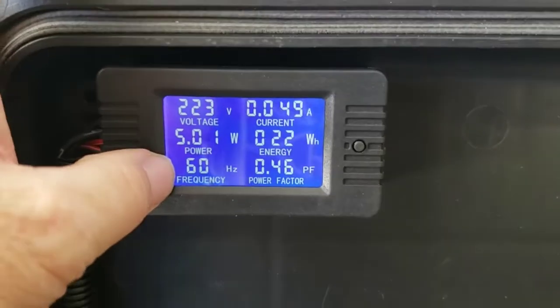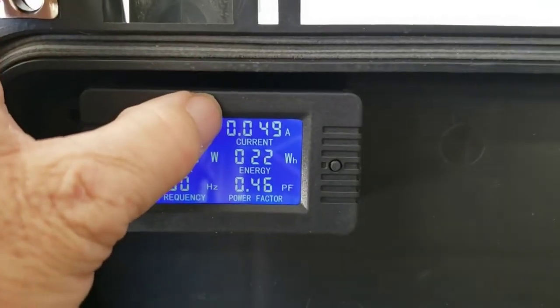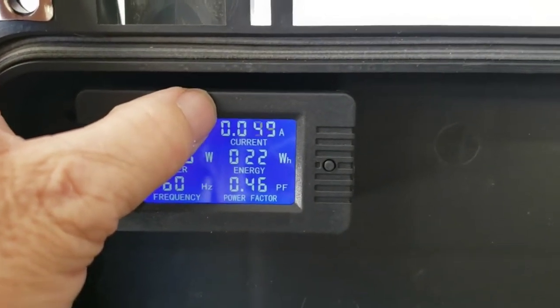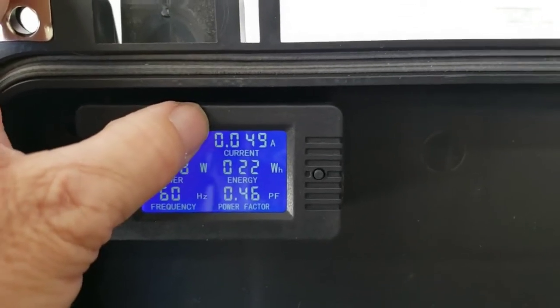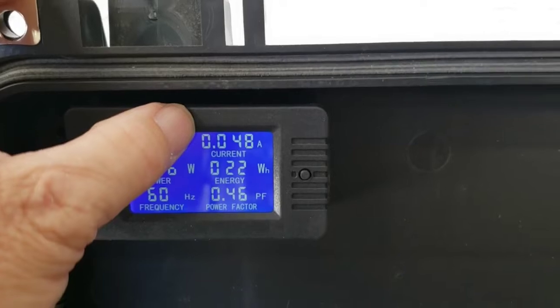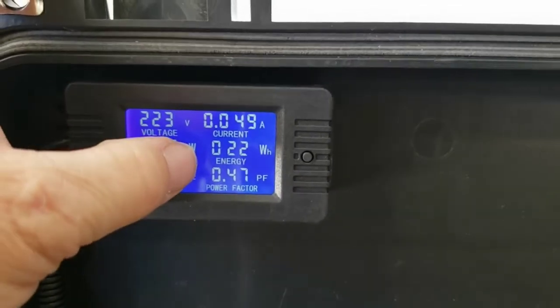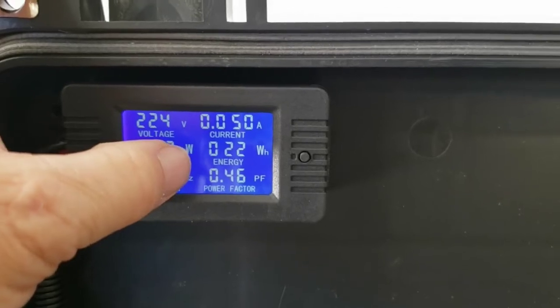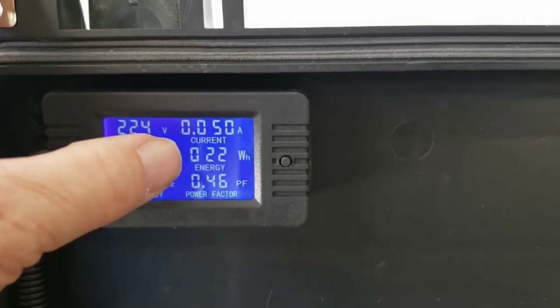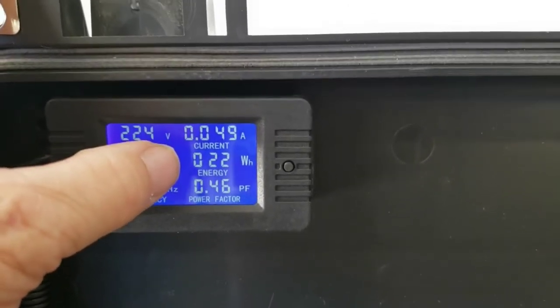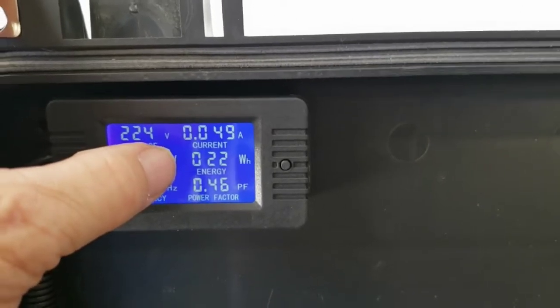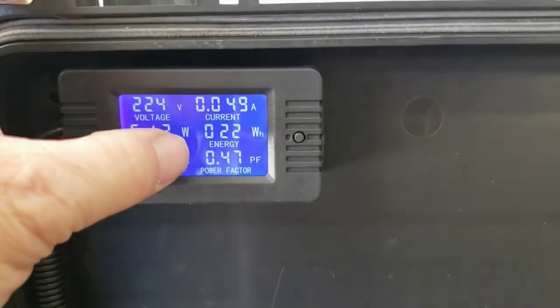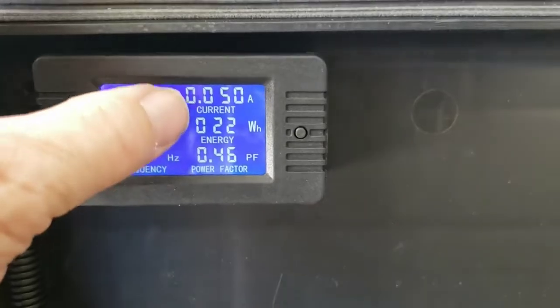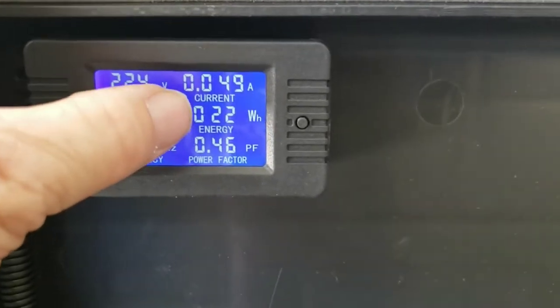Line frequency, 60 hertz of course. That'll display the amps that you're currently drawing at the 240 volt range. So keep in mind that does go up about double on the 120 volt side of things. And we do only have a 350 VA transformer in here, so it really isn't designed to go more than about 2-3 amps on the 120 volt side for more than a couple minutes. So keep that in mind. Don't run this long term.